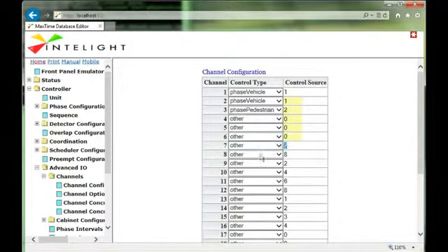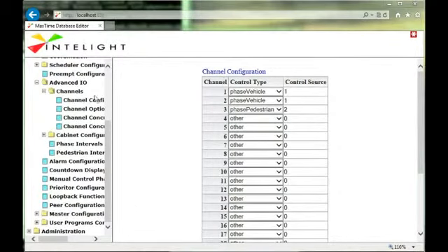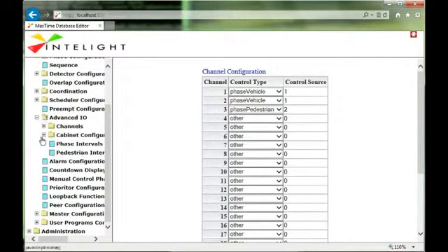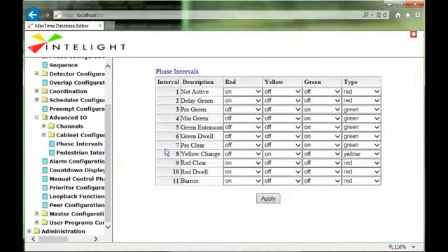So certainly take a look. Load switch 1 and load switch 2 are both phase 1, but we're going to wig-wag the reds. That's why we need 2 load switches. So when one red's on, the other one's off, and vice versa. So all you really need is a two-phase load bay with 4 load switch sockets. You can use 3 and have a spare. The next step is that pre-clear value. Right now for the pre-clear, we want the yellow to be alternate flashing so that we can flash that. We hit apply, and that's our programming.